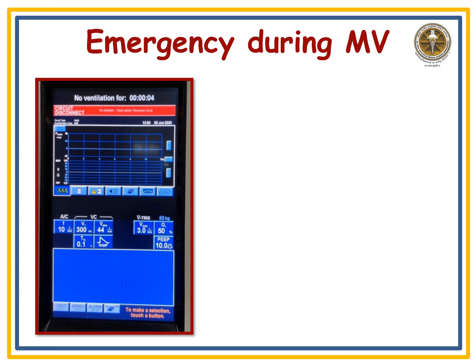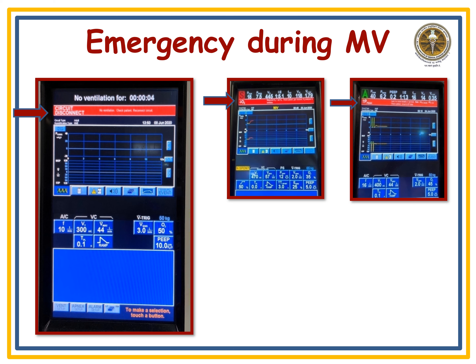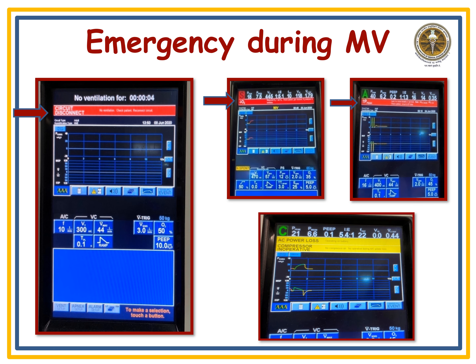During mechanical ventilation you may face emergency situations — if not attended to promptly, these may lead to mechanical ventilation failure. Problems are identified through alarms. When there is a problem, the ventilator gives alarms in the form of colored lights and written instructions on the screen. Red alarms include: circuit disconnect, low oxygen supply, and high peak pressure. Yellow alarms include: AC power loss and compressor inoperative.